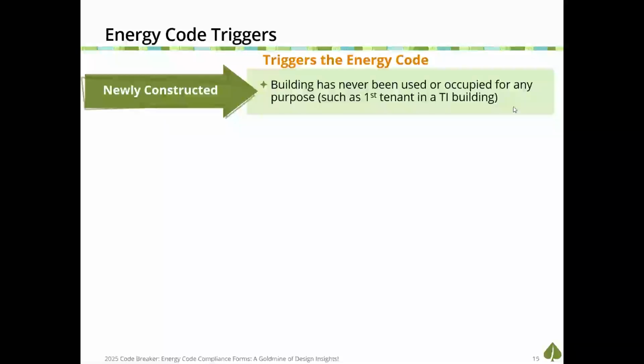That can be very difficult. Right now, if I have a TI building built 10 years ago and the very first tenant moves in—this happened to me on at least 5 projects last year—they trigger the PV and battery requirements of the 2022 code cycle, because it's a newly constructed building with an occupancy that triggers those requirements. It's really hard to figure out how to put PV and battery into a building that's already built and never took those features into consideration.